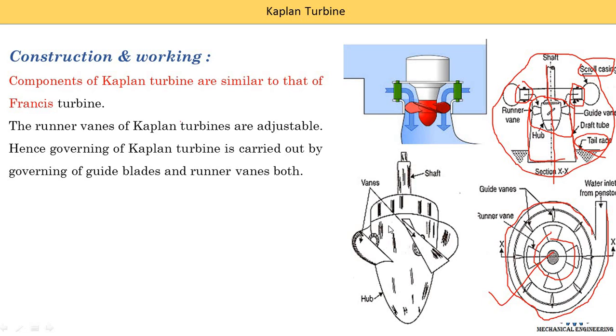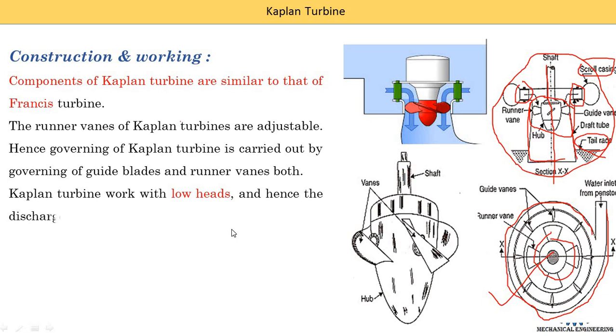Kaplan turbine and propeller turbines are similar, but in a propeller turbine the runner vanes are not adjustable — that is the only difference between propeller turbines and Kaplan turbine. In a propeller turbine the runner vane angle is not adjustable, but in a Kaplan turbine the runner vane is adjustable. The Kaplan turbine works with low head; hence the discharge for the Kaplan turbine is high — it is used for low head and the water quantity required is high.